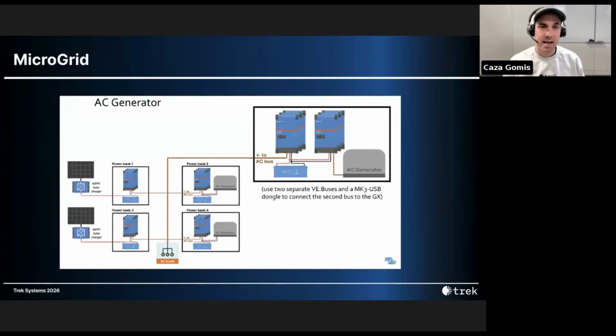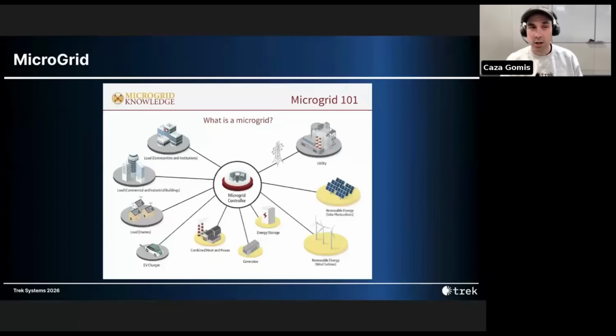In this example, we have a traditional AC generator in the top right corner with a Victron system there to supplement. Let's say an industrial campus wants to expand without needing to completely revamp their energy system. Well, now you can drop in these additional power banks, some utilizing solar and others with a DC generator backup. And all will work together to support the same AC load requirement. And the icing on the cake is that you do not need to run additional communications cables to get these power banks in sync.